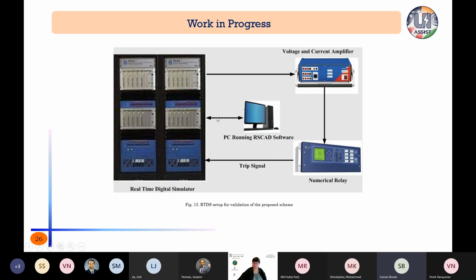So here the computer is connected to the RTDS with an Ethernet cable, so communication will be there. And also we have GTAO cards, that is GT analog output. So the real-time voltage and current signals will pass to the voltage and current amplifier, so that the numerical relay gets the proper voltage. For example, for this SEL-451, if we exceed the 6 volt peak value, then this relay will get damaged. So there is a necessity of a voltage and current amplifier there. If this voltage and current amplifier is not there, then we need to make some ribbon cable arrangement, for the safety of the device.